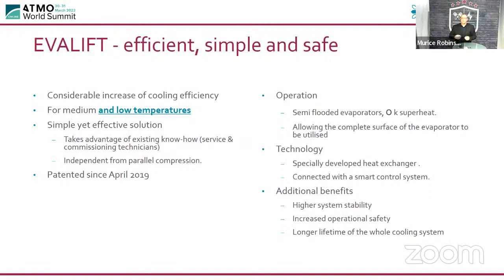So the nice thing is bringing the superheat down to almost 0 K. So we have a flooded evaporator. This enables the whole evaporator to actually be used instead of wasting that superheat as part of the evaporator. The technology basically is a specialized and specifically developed heat exchanger for this type of system, and a very smart control system. Additional benefits of the EVALIFT system are higher system stability, so your system becomes very stable. The operation is also very safe, so you don't have to worry about having any issues with your rack, and you have a longer lifetime of the whole cooling system because of these factors.